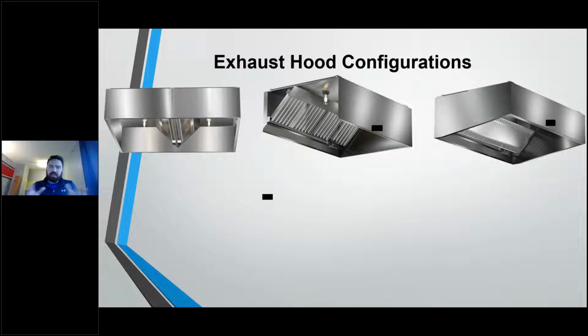And one thing, again, it's very basic, but one thing that I should mention is that code is going to require an overhang to the appliances for these hoods of a minimum of 6 inches from the edge of the appliance. So you're going to take your entire appliance lineup, the total length of your hood, your fryers and your griddles and whatever you're protecting. And then you're going to add a minimum of 6 inches to both sides of that hood, or a minimum overhang of 6 inches to the front of that hood. And we'll go into some different design considerations on that later.